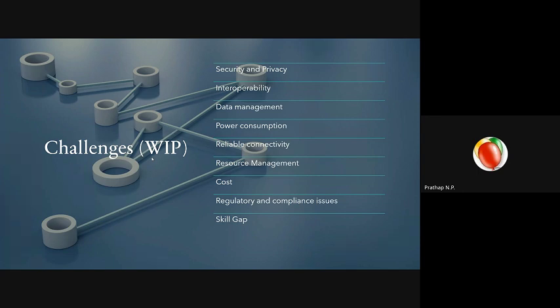Another thing, going back to security and privacy, is password rotation. In a substation you'll have at least 70 to 80 IEDs, each with its own access levels - level 1, level 2 - depending on who's accessing it, with different features enabled. But you can't keep one password, because hackers can figure it out and crack it. So there's separate password management software that takes all the passwords and rotates them, giving new passwords. You can set that, but it's not done automatically.